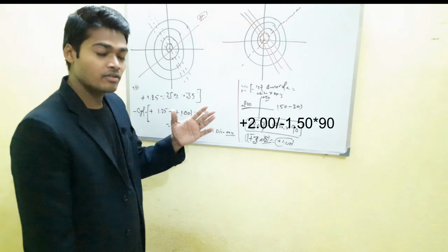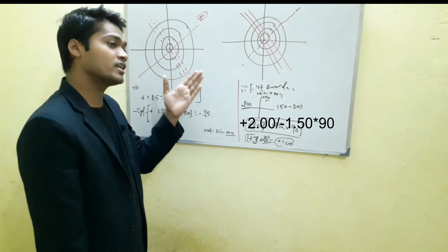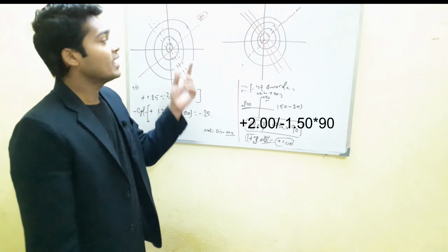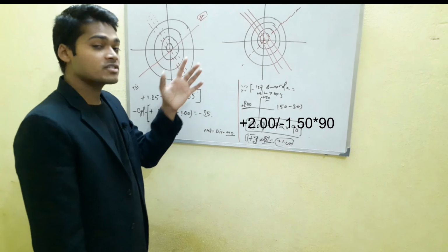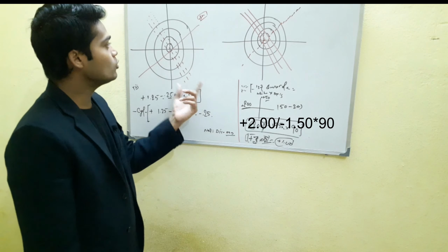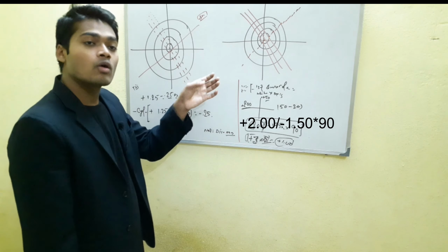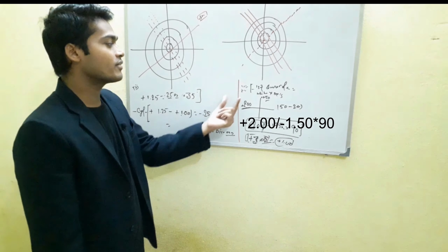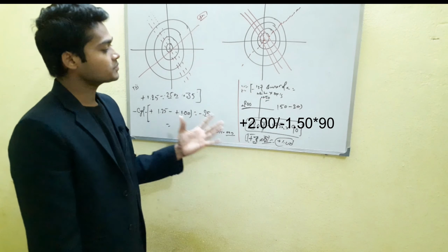If the whole set of lines gets prominent at the same power, it means the lens is spherical. If only one, it means spherocylindrical. Then write the first power, using whichever method you want, as you have two choices. Then go further to the minus side, and you find the three bars getting clear again, then write it down.